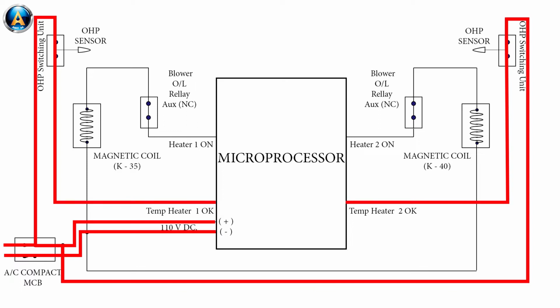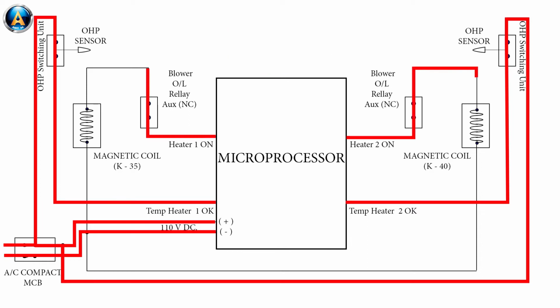Whenever the coach inside air temperature comes down below 19 degrees centigrade, a 110 volt DC signal is generated at this terminal of the microprocessor. And through this line, this signal or 110 volt DC power reaches the magnetic coil of K35 and K40 contactor. And simultaneously, a magnetomotive force is developed there for closing the main contact.